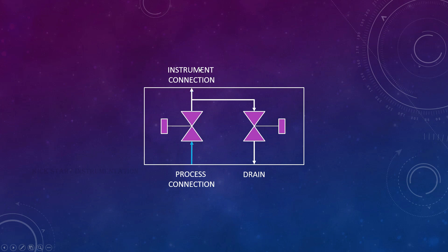Once completely drained, you can safely remove the instrument and take it to your laboratory for calibration or any other work. Once you finish, the process is repeated: connect the instrument, connect the process medium, drain the air bubbles, and so on. This is how a two-way manifold valve functions. Thank you friends — see you in the next video.